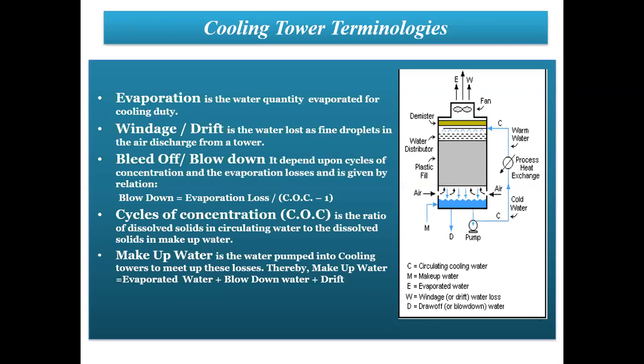The third one is blowdown loss or bleed-off loss. This is the amount of water we need to bleed off from the cooling tower drain valve to maintain a proper cycle of concentration, and also to maintain the recommended parameters of the cooling tower water.